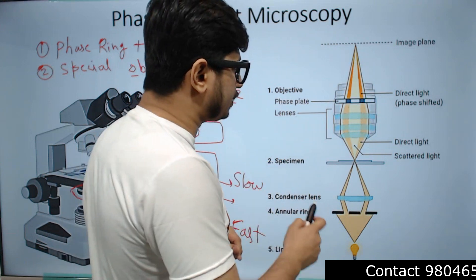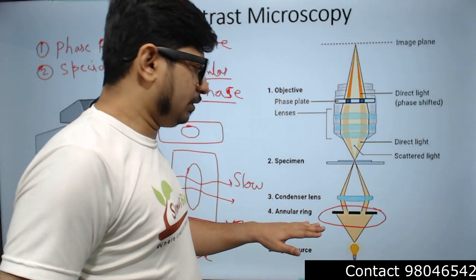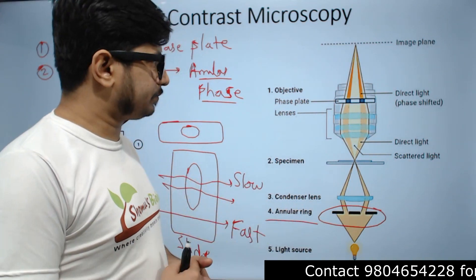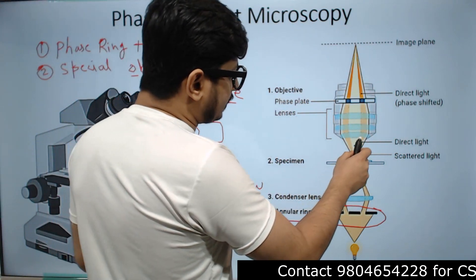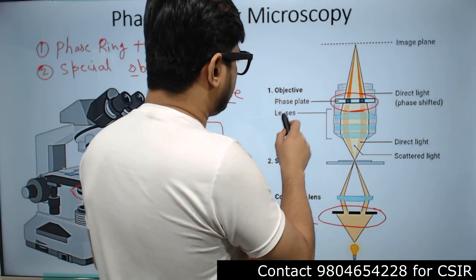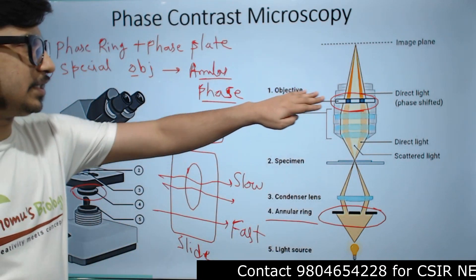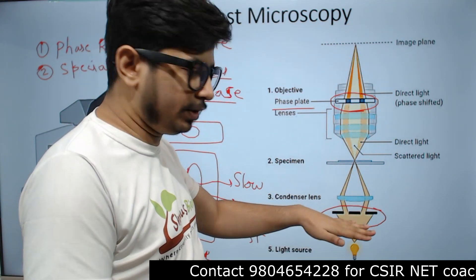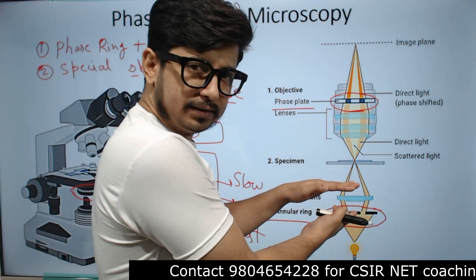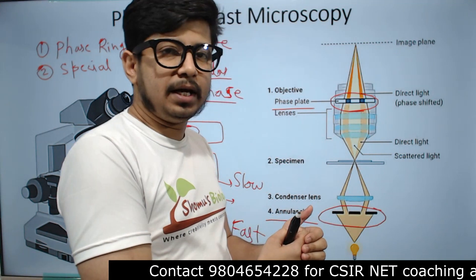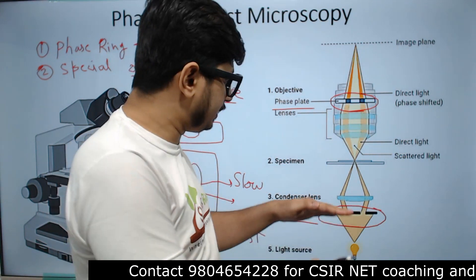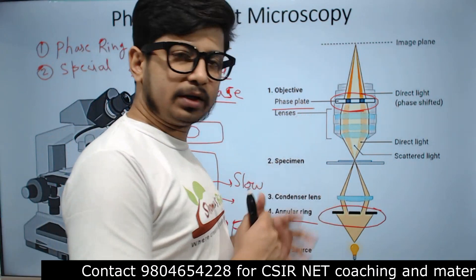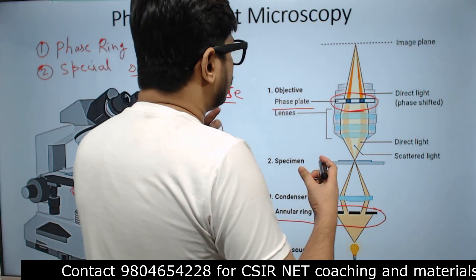There are two new components. One is the phase ring, also called the annular ring, and the other is the phase plate present inside the objective lens itself. The phase ring or annular ring is present near the light source, just right after it, along with the condenser — beneath the condenser. These are the two components unique to a phase contrast microscope.